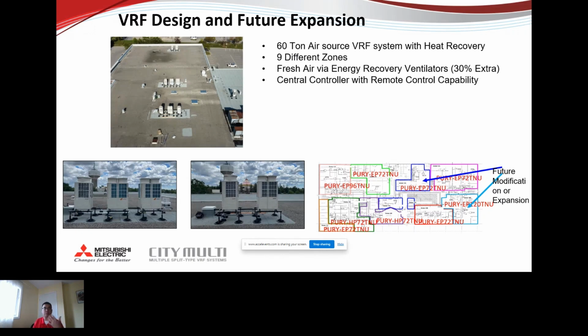Heating, on the other hand, seems to be very on par with what they did 30 years ago, which is very good. But my personal experience is that it is a lot more challenging to add cooling after the fact compared to heating, right? Because for heating, you can have a baseboard heater, you can bring a personal heater to the office, but for cooling, it's very hard to add after the fact. So I often say, even though heating is very important, don't overlook the cooling side of things. And we were able to divide the entire office into 9 different zones.